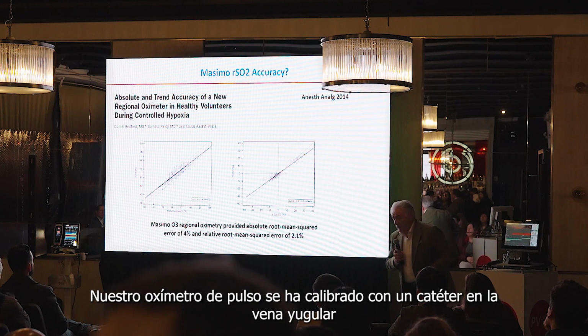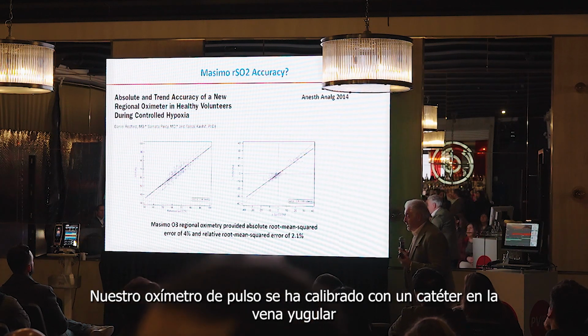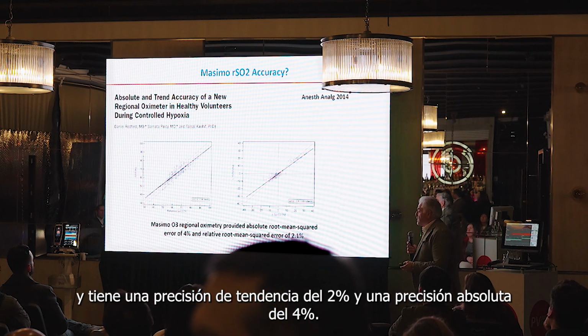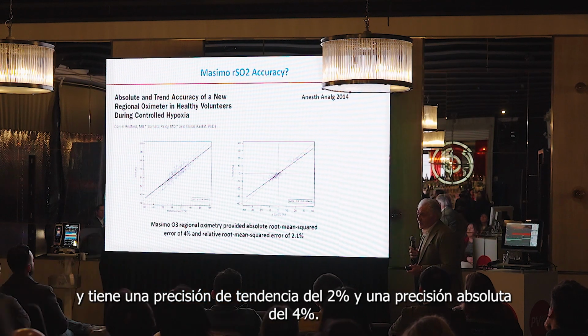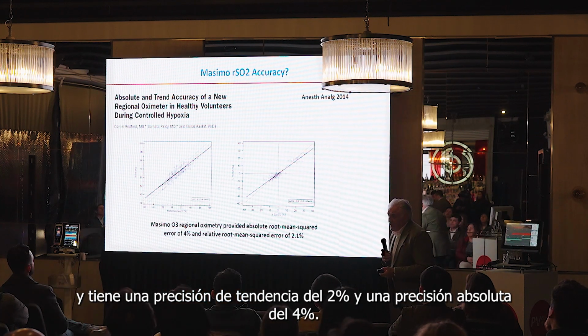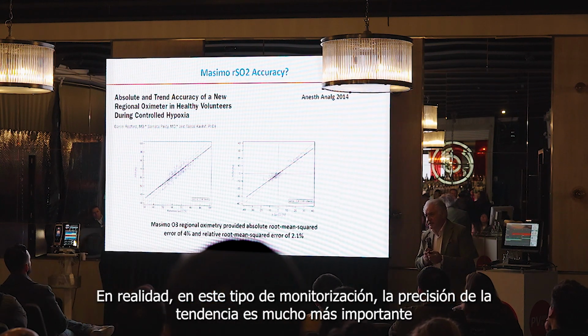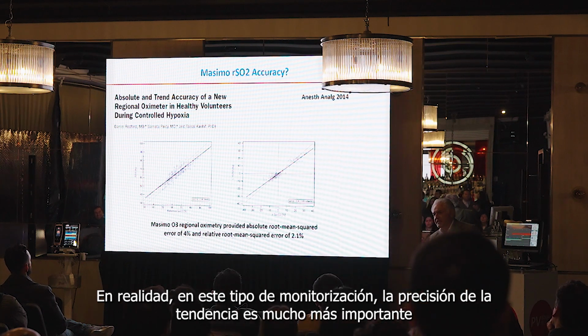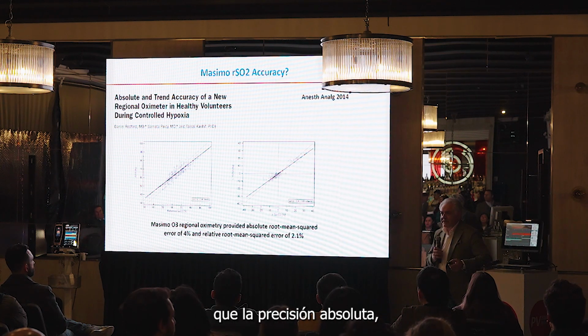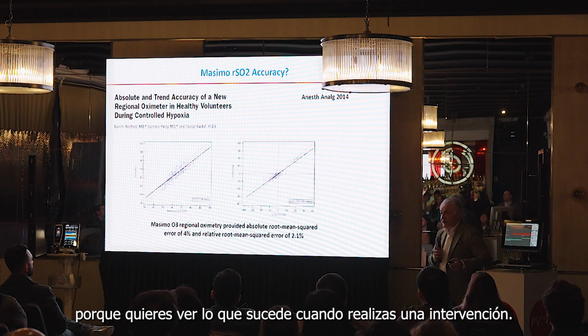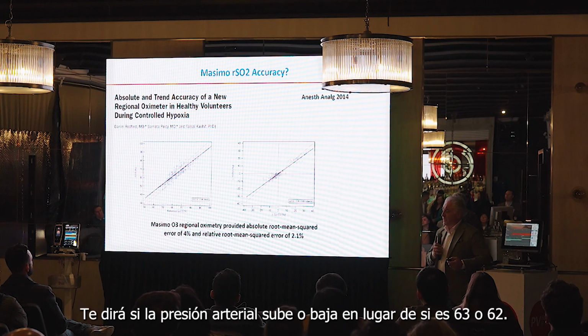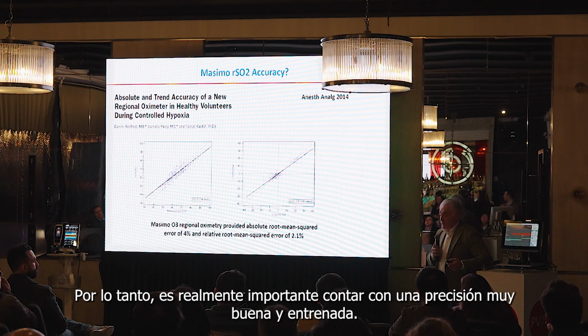Our cerebral oximeter has been calibrated against a jugular bulb catheter, and it's got a 2% trend accuracy and 4% absolute accuracy. And really, in this kind of monitor, trend accuracy is much more important than absolute accuracy, because you want to see what happens when you do an intervention. So if I drive the blood pressure up, does it go up or go down, rather than whether it's 63 or 62? So it's really important to have a very good trend accuracy.